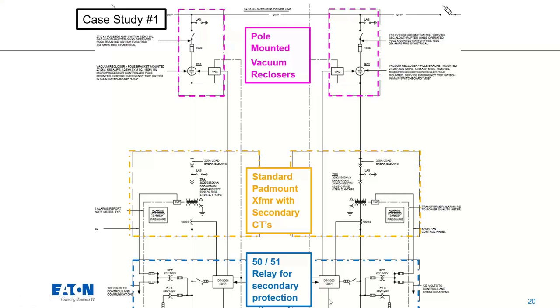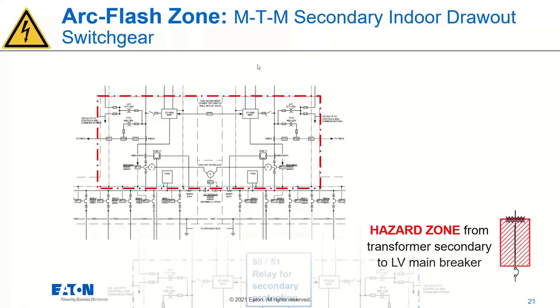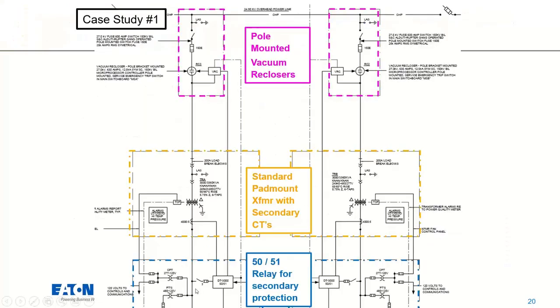So this next slide is just moving down on the single line. What I just showed was just above here, feeding this. So this is our draw out switchgear that we're going to analyze. What we're looking at right now is between that draw-out switchgear, so ahead of that main breaker, and all the way upstream to the next most protected device. So, going back again, that's this pole-mounted vacuum recloser right here. If we go all the way up the line, there are no other protective devices that can be tripped in any way, besides this recloser, and then ultimately the fuse ahead of that.